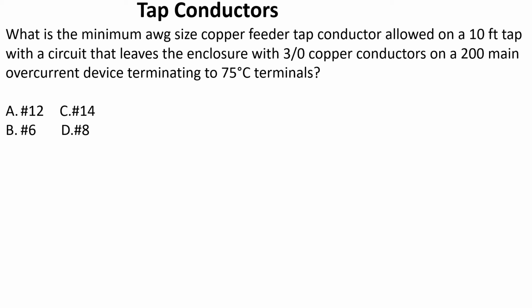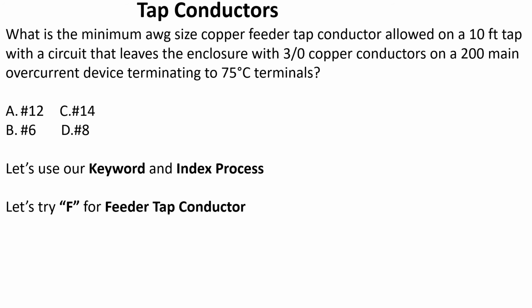What is the minimum AWG size feeder tap conductor allowed on a 10-foot tap with a circuit that leaves the enclosure with 3-aught copper conductors on a 200 amp main overcurrent device terminating to 75°C terminals? So there's a lot going on here. Let's use our keyword index process and break it down. So let's try F for feeder tap conductors. If you look at the overall theme of this question, it's asking about feeder tap conductors. It's asking about size, and it's got some different information in there that might lead us in the right direction. So, okay, let's head to F.